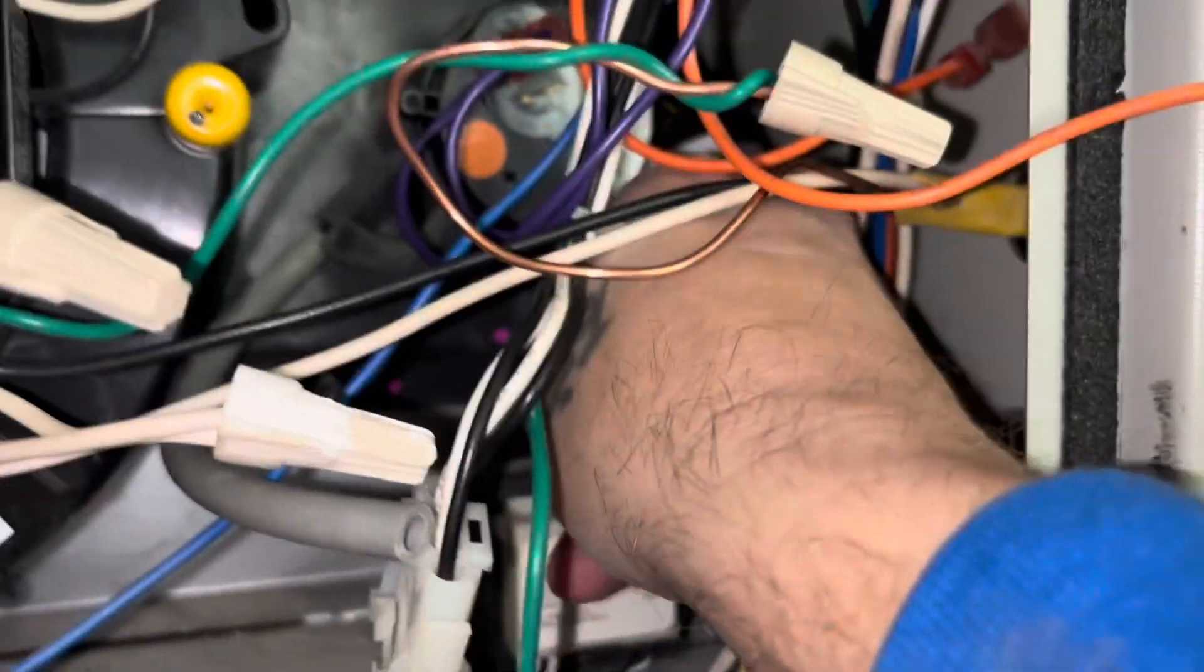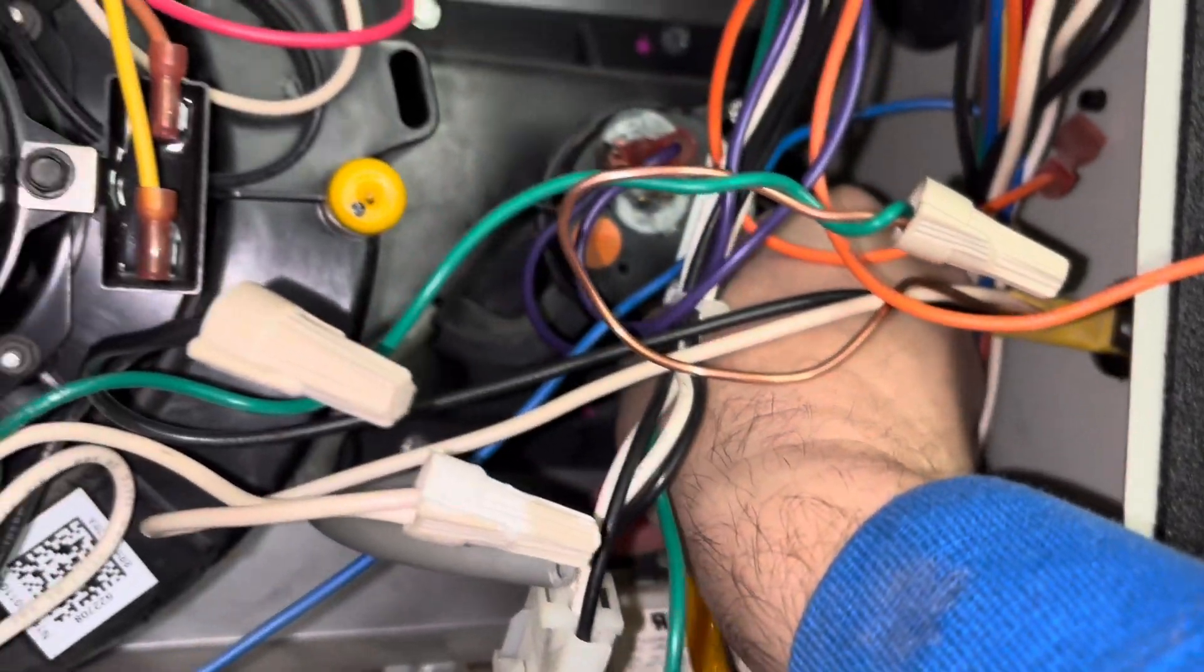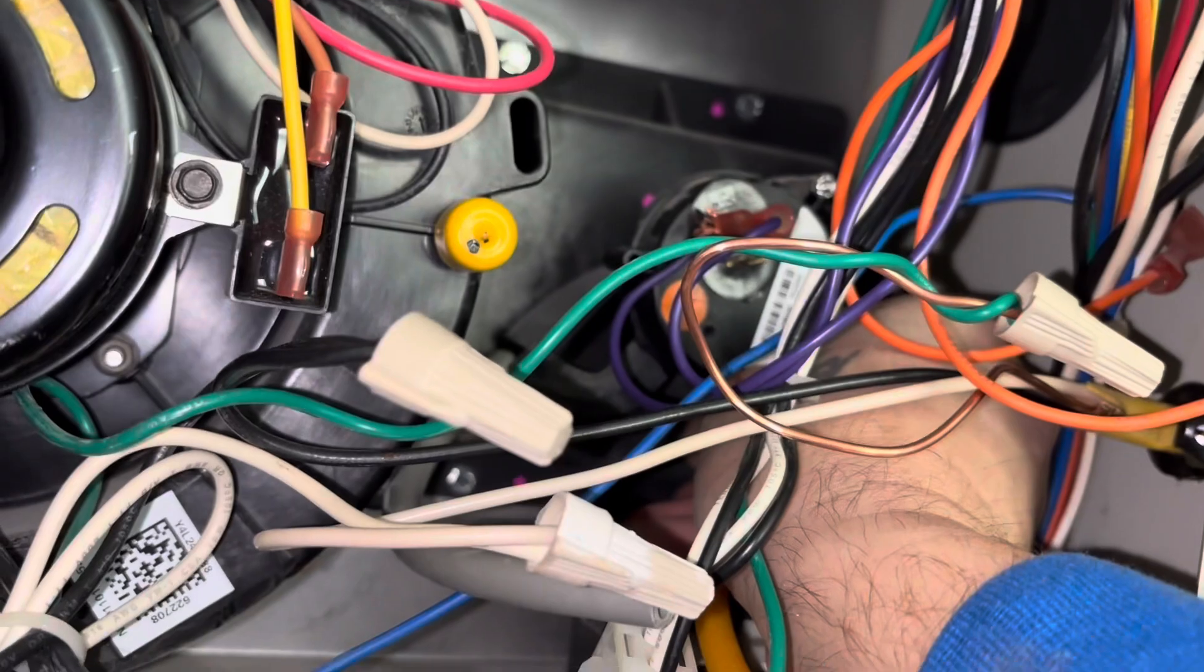I also, I don't show it on camera, but I do clear the condensate. I blow into it, and then I make sure I blow through it to make sure there's no debris or anything in there. A very thorough way to do it would be to remove the draft inducer and remove that black piece of plastic there, and just make sure you get everything cleared out of there. We don't need to do that in this service call, but sometimes you do if it's really badly clogged.